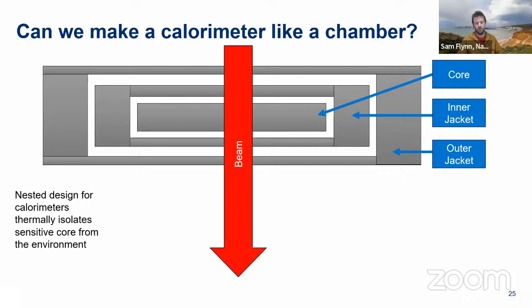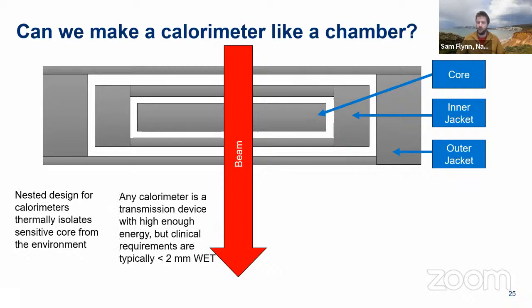Now, you put a beam through it and you're going to lose a lot of it due to attenuation. If you're being very, very pedantic, this is technically a transmission device. The FAST-01 study we did with Cincinnati, this was the proton calorimeter. It's about 5 centimeters thick, about 10 centimeters water equivalent. It is a transmission device because it was operated in the plateau. So if you had a patient behind it, maybe you could, but that doesn't satisfy the clinical requirements for what a monitor chamber is. Typically that's 2 millimeters water equivalent thickness or less being ideal.